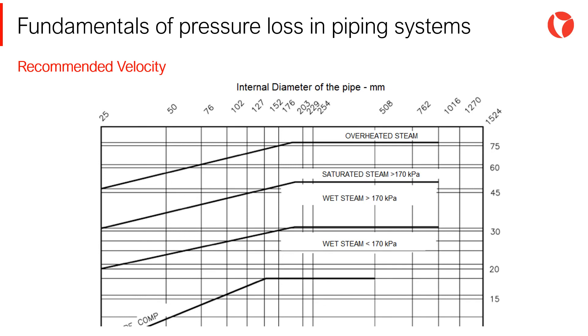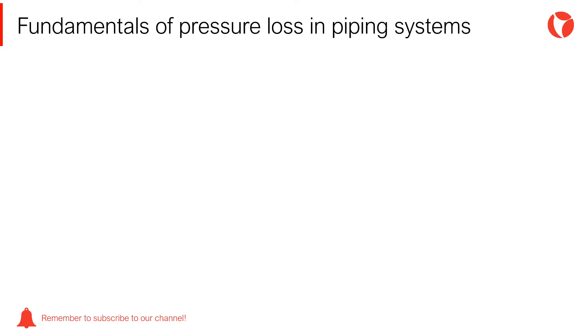From all the values mentioned, normally the parameter fixed is the velocity, since the diameter and pressure loss are a function of this. There are several publications and references that collect data from successful experiences, allowing designers to develop different projects. An example of this can be seen on screen for steam. There is not a unique solution when it comes to pipe sizing — there are different solutions that bring different implications.